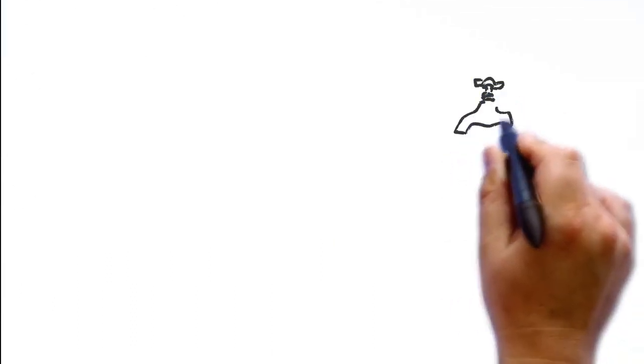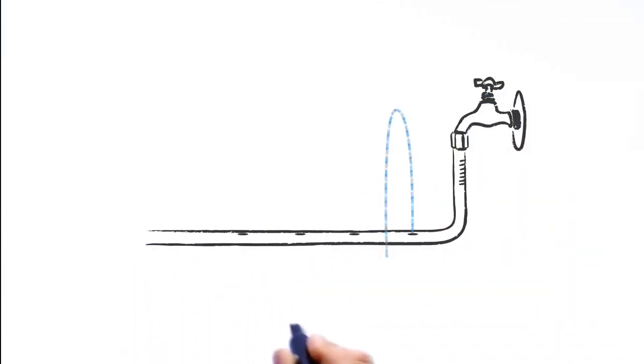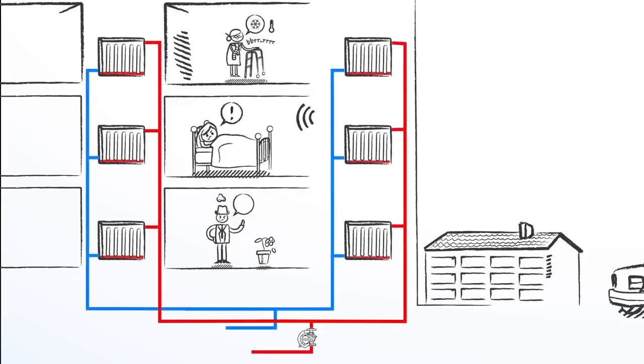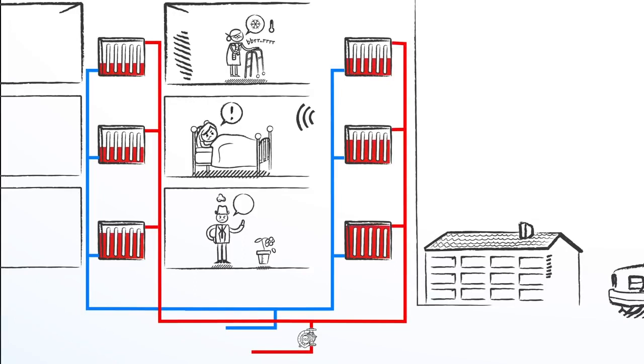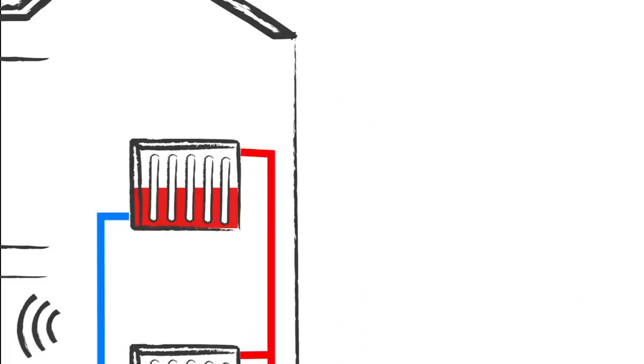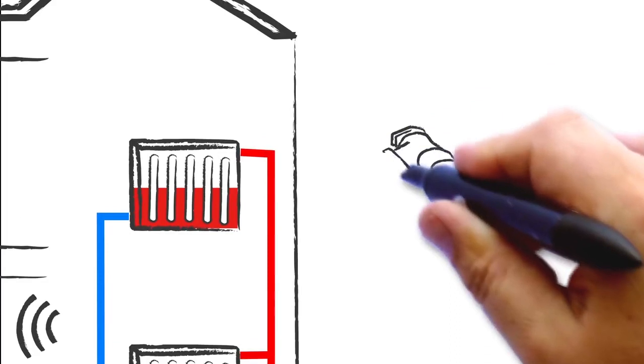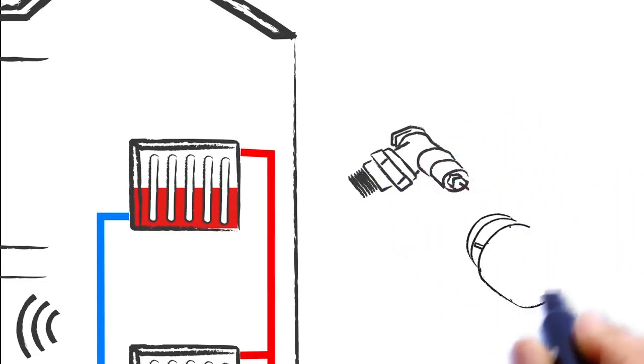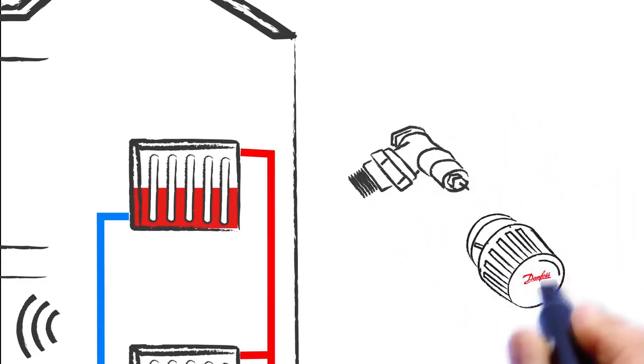Water follows the path of least resistance and takes the shortest route. In heating systems, we see the same thing happening. To compensate for this, we have pre-setting on radiator valves, which ensure the right flow throughout each radiator valve.